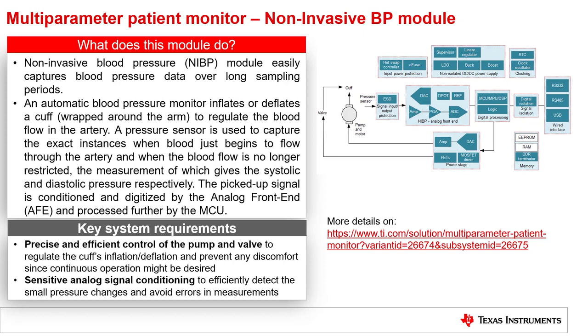The key system requirements for the NIBP module are: precise and efficient control of the pump and valve, to regulate the cuff's inflation and deflation and prevent any discomfort since continuous operation might be desired; and sensitive analog signal conditioning, to efficiently detect small pressure changes and avoid errors in measurement. A common block diagram for such NIBP modules is also shown in this slide.